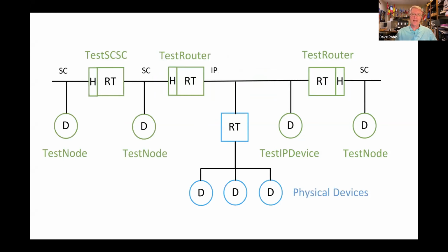And because we can, on IP, I dropped in, for the purpose of these demos and tests and all the screenshots I did here in my office, an actual IP router and a bunch of MSTP devices over there. So they'll show up when we do whois testing and read property testing and stuff. You can see actually routing from any one of those green devices back and forth to the blue physical devices on the other side of another router. So that's our test setup.